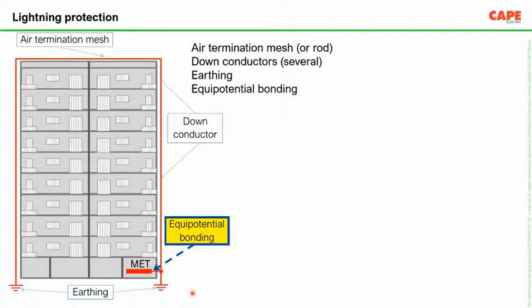So the SPDs have to be installed at different locations in your electrical system so that a very good equipotential bonding is created. Basically, SPDs are used to create equipotential bonding between earth and a live conductor, a current carrying conductor. So if you have external protection, your building is protected. If you have an equipotential bonding system with SPD, your equipment is protected. The next subject is, of course, shielding of the wiring. Long wirings, you need to follow certain shielding rules. If you do all three, your equipment will definitely be protected.